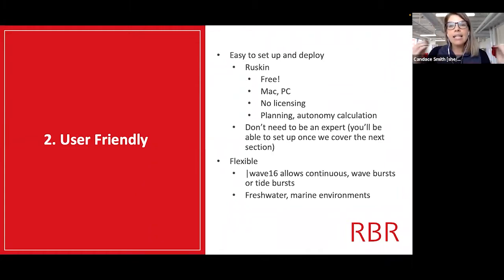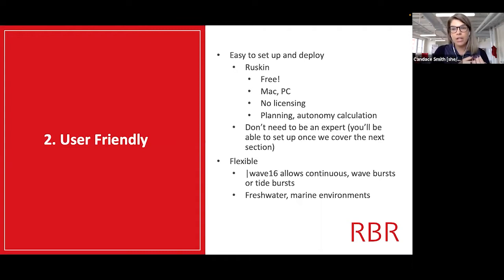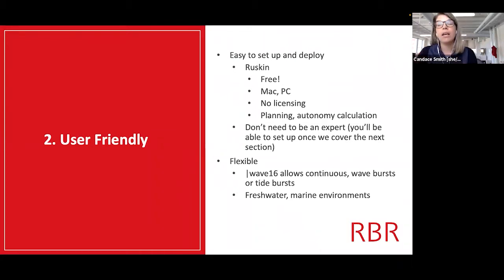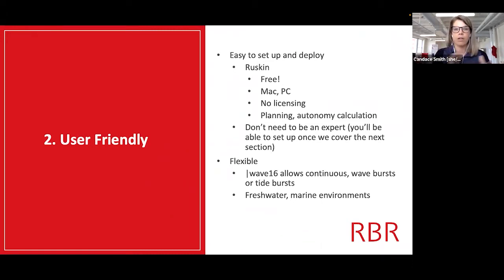The easy-to-set-up piece is really Ruskin — it's super easy to do it there and it's really flexible. The Wave 16 feature actually allows you to do continuous sampling or wave or tide bursts. Continuous sampling gives you continuous pressure data — that's how we measure waves at RBR. Or you can do the wave sampling, which gives you burst data and all of these different parameters, like significant wave height and significant wave period. You can also use the instruments in freshwater or marine environments — they can be used in any environment.